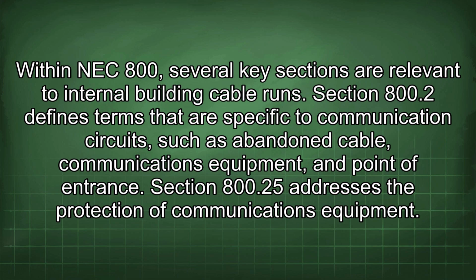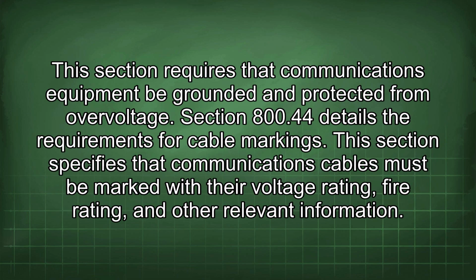Section 800.25 addresses the protection of communications equipment. This section requires that communications equipment be grounded and protected from overvoltage. Section 800.44 details the requirements for cable markings. This section specifies that communications cables must be marked with their voltage rating, fire rating, and other relevant information.